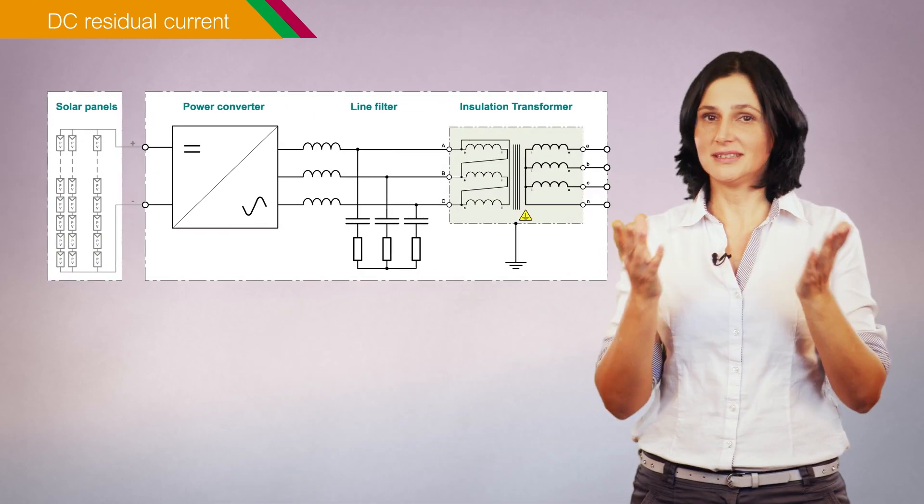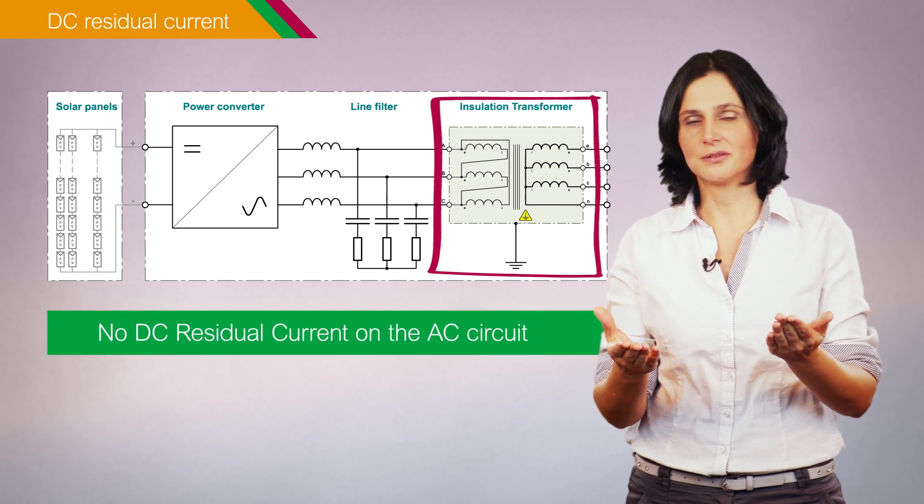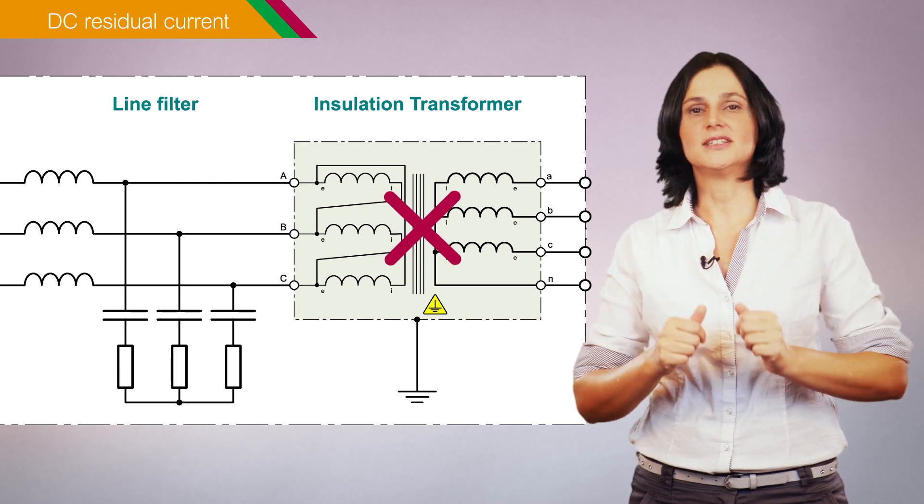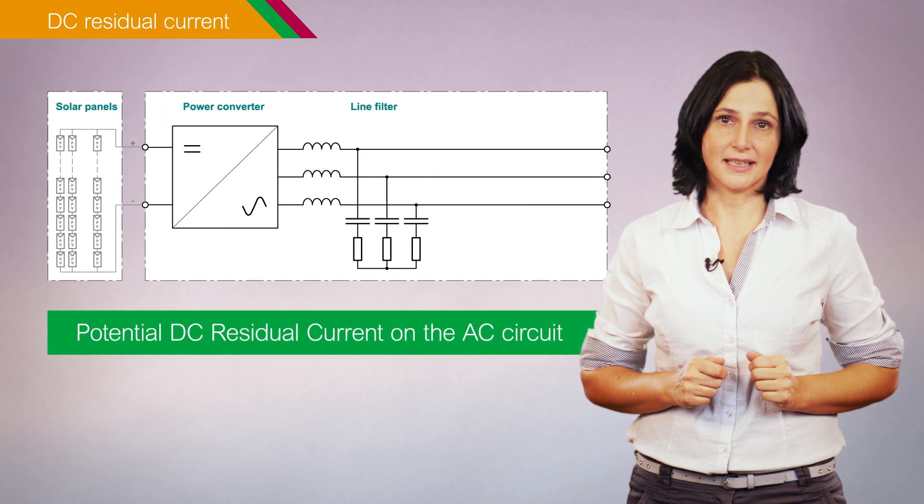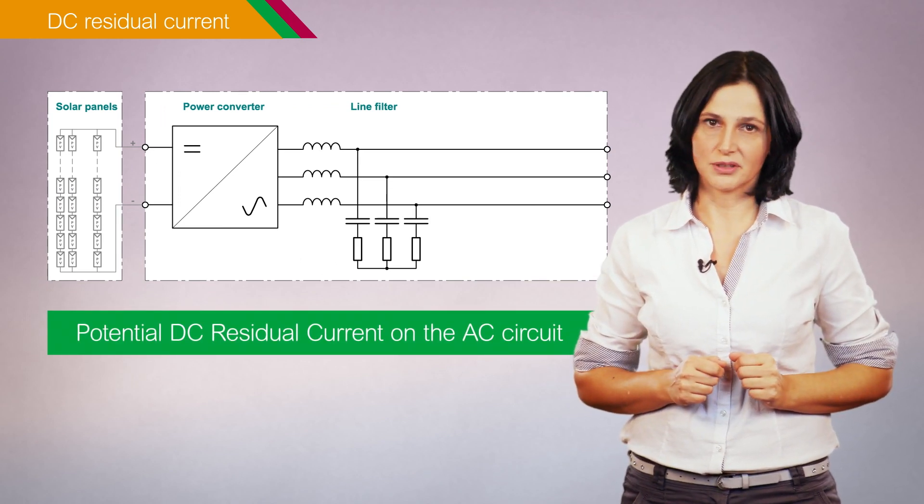Photovoltaic inverters may generate DC residual current in the AC circuit depending on their technology. There are two types of photovoltaic inverters: inverters with insulation transformer which cannot inject DC residual current on the AC side, and inverters without galvanic isolation which inject DC residual current on the AC side unless measures to prevent this are taken by the inverter manufacturer.